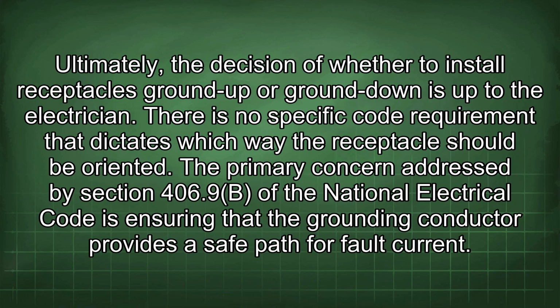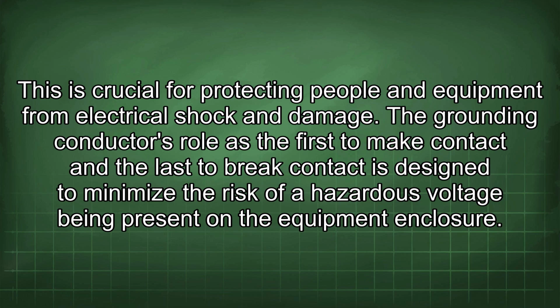Ultimately, the decision of whether to install receptacles ground up or ground down is up to the electrician. There is no specific code requirement that dictates which way the receptacle should be oriented. The primary concern addressed by Section 406.9b of the National Electrical Code is ensuring that the grounding conductor provides a safe path for fault current. This is crucial for protecting people and equipment from electrical shock and damage.